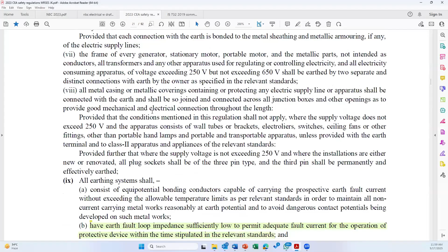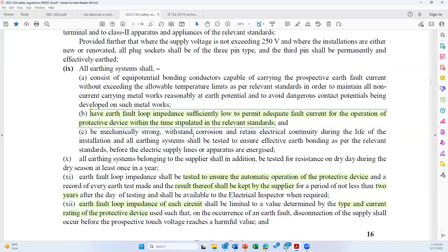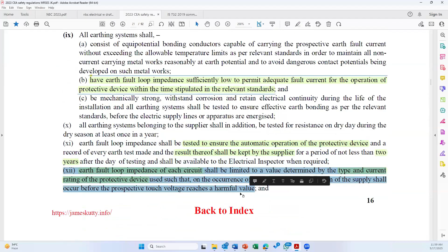Now going back to the CEA regulation, the old concept, there is a phenomenal change in the CEA regulation in this particular case. For example, have earth fault loop impedance sufficiently low to permit adequate fault current for the operation of the protective device within the time stipulated in the standard. Number 11, earth fault loop impedance shall be tested by the supplier. Number 12, earth fault loop impedance of every circuit has to be verified. And for example, if you go to the annexure, let me search. This earth fault loop impedance has been included in multiple places. I'm just searching the annexure in Schedule 2, where the testing of earth fault is also necessary.